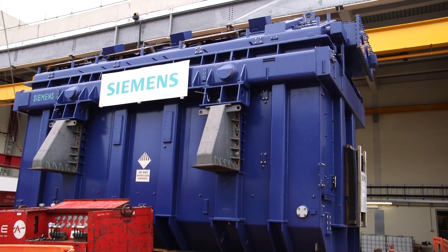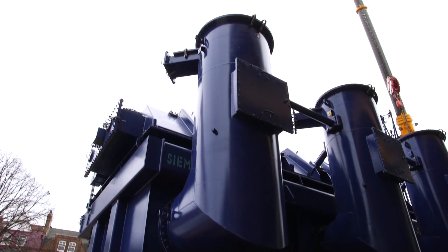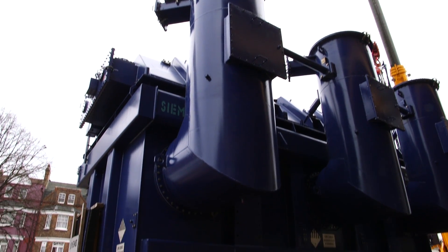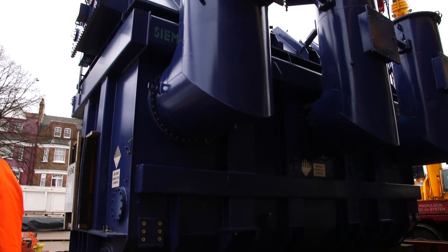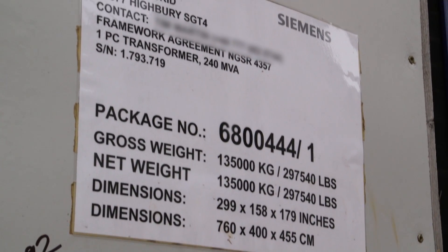And yes, there it is, outside, waiting to be installed. I'm currently standing where this 135 tonne transformer will soon be present inside the transformer bay. This 400kV transformer transforms the voltage from 400,000 volts to 132,000 volts, which will eventually connect into the substation.